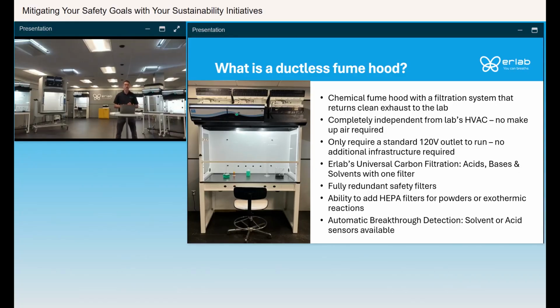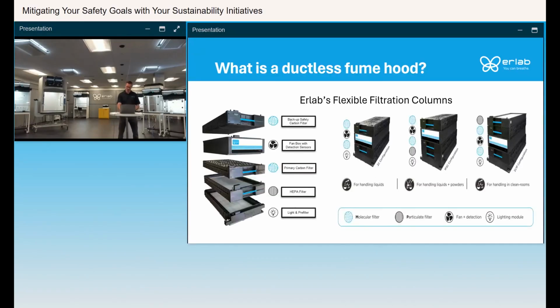It also gives you the ability to add HEPA filters in case you're working with any toxic powders, creating any exothermic reactions, or doing acid digestion where you need the particle capturing efficiency of a HEPA filter. Our hoods are also equipped with automatic breakthrough detection. So there's a solvent sensor on every hood that's going to constantly monitor the performance of the main carbon filters, constantly sample the air as it passes through them, and will alert you to any potential breakthrough. And that's why having this fully redundant safety filter on the hood is so important.